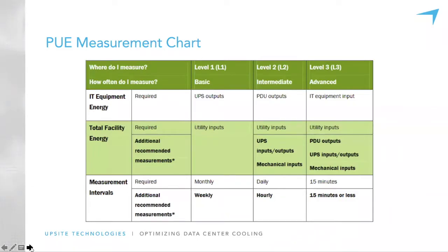I was so concerned that I would do my PUE measurement wrong. Really, the only way you can do a PUE measurement wrong is if you cheat the numbers, if you see your total facility energy or total IT equipment energy and fudge the numbers so your PUE looks better. But if you are recording and following the exact outputs and energy usage you see on both your IT and your facility equipment, you're not going to be wrong.